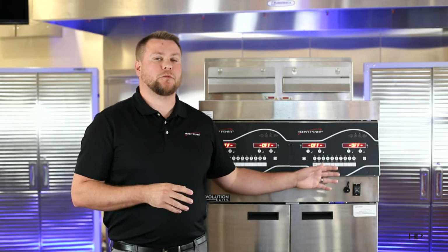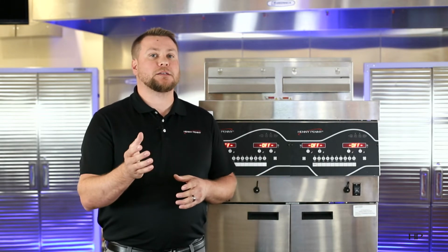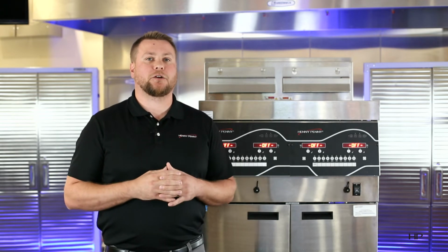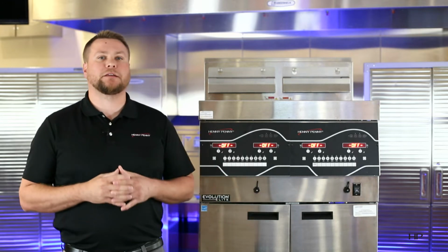Now what we see most likely is causing the problem is the encoder motor itself. The reason being is because there's roughly 2,000 encoder sensors inside that encoder motor itself, checking for all those. So usually what we see is it's not delivering that feedback back to the AIF board. If our motor is turning when we turn this on and we can hear it, we know our voltage is there, but we're still constantly getting the E82D error code, then this is where we would want to start with replacing that encoder motor. In very rare situations is it actually going to be the AIF board, but we can't rule that out.